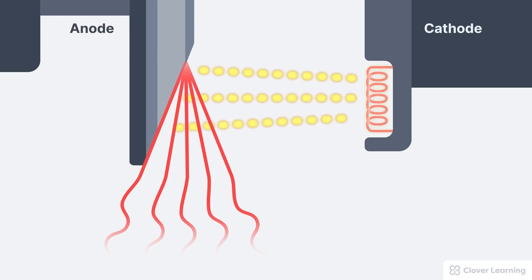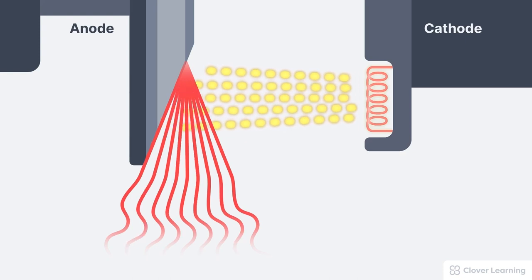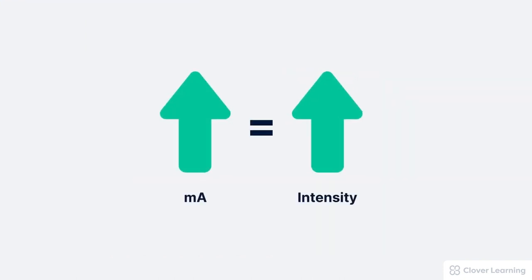The process of creating the x-ray tube current starts at the cathode filament. Setting the MA at the control panel is the primary factor controlling the amperage applied to the filament. As we increase the MA, this increases the filament amperage, which increases thermionic emission, increasing the number of electrons created, which are then available to flow across the x-ray tube and collide with the anode, creating x-rays. So tube current actually starts with thermionic emission and the filament current.